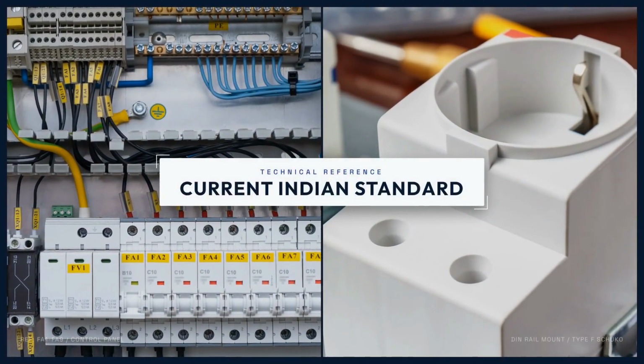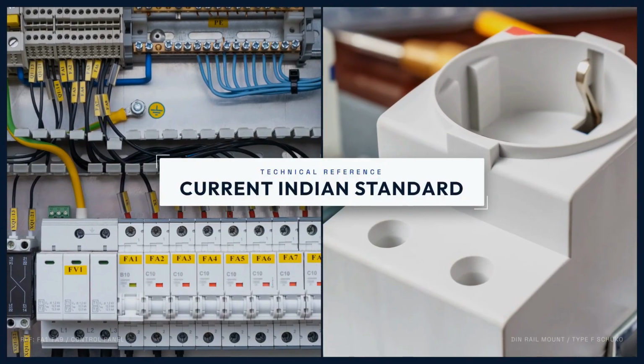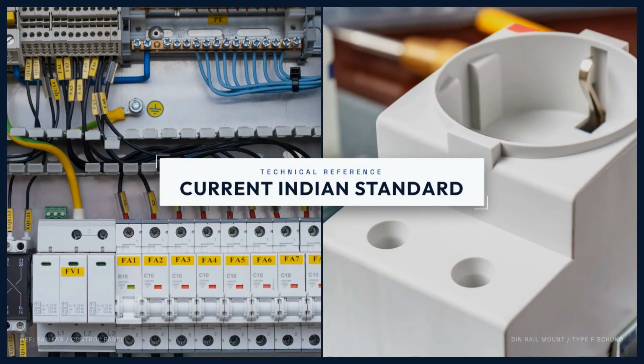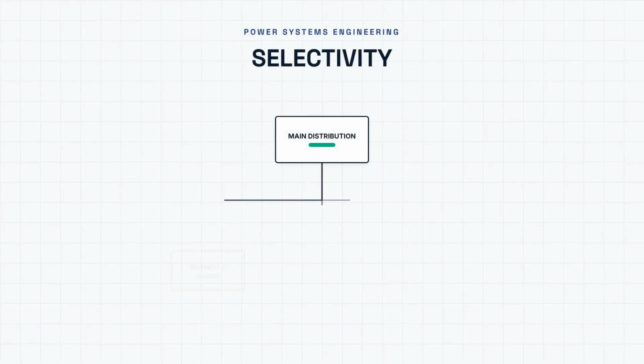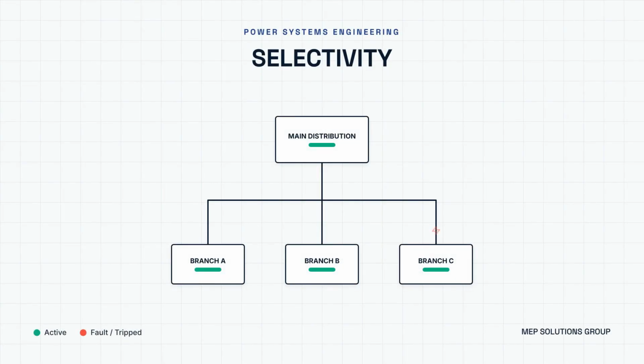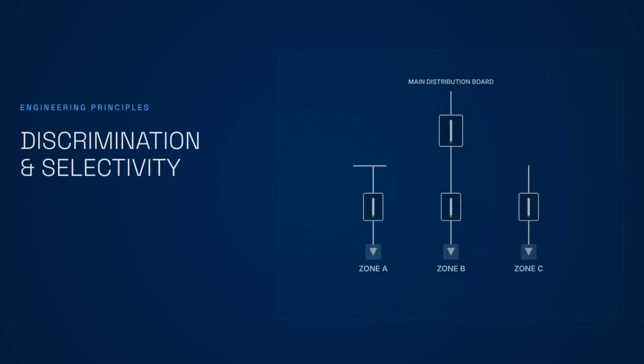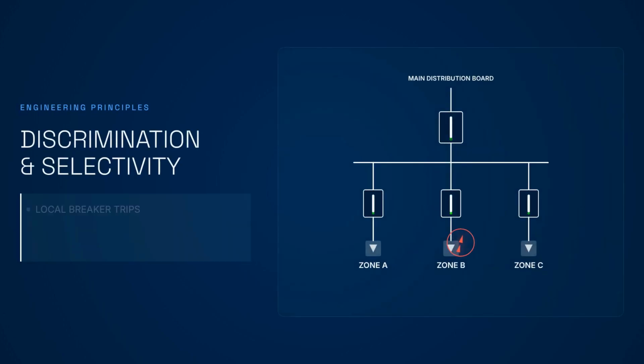It also recommends socket outlets with suitable circuit breakers to a current Indian standard for industrial and commercial use. And it updates protective device coordination - the way your breakers discriminate and cascade so that when a fault happens, only the nearest device trips, not the whole building. Good coordination is the difference between one circuit going dark and the entire floor going dark. The code now expects you to design that properly.